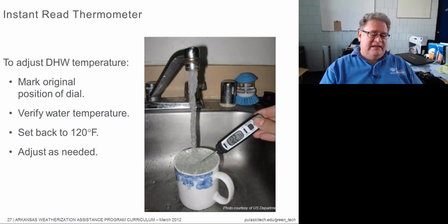I would say, hey, if you're going to move that thing, make sure you set it no higher than 120 degrees. If they want it at 130, set it to 120. Show them where the 130 is approximately. Put a mark on there that you know you put at 120. Take a picture of it and let them move it afterwards. Don't move it back up to 130 for them. From a liability standpoint, either don't touch the thing or set it back to 120. From energy efficiency, 120 is a pretty good place.